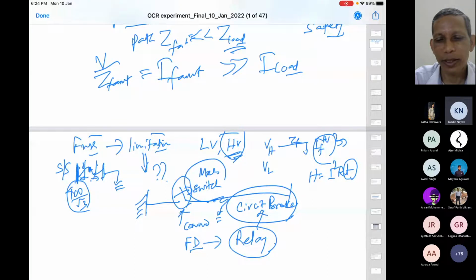Yeah. A circuit breaker is a mechanical device. Think about simply two plates. They have to be opened, and this physical isolation is required so that the separation can sustain the normal system voltage, the nominal voltage. So the mechanical separation of this side plate and that side plate is essential. For that we require a switch, a mechanical switch.